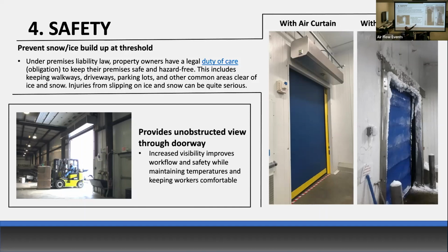Over here, you can see the ice buildup. I'm not even going to get into this, but we have a special line of air curtains for coolers and freezers. I know a lot of mechanical engineers, it's a specialized segment if you do cold storage. Completely different presentation, but if you do work on cold storage, we do have a line of air curtains specifically for that. This is crazy, and I don't even understand how it works myself, but for the freezer air curtains, we actually use an electrically heated air curtain on the warm side to prevent ice, condensation, frost from building up inside the freezer.